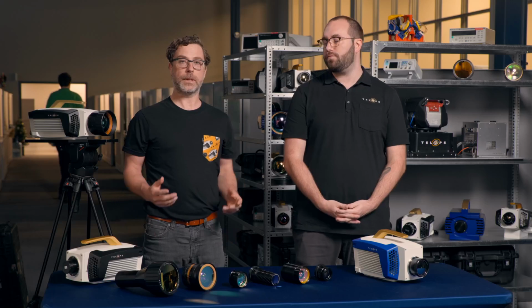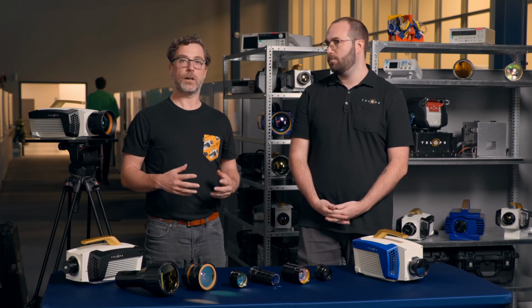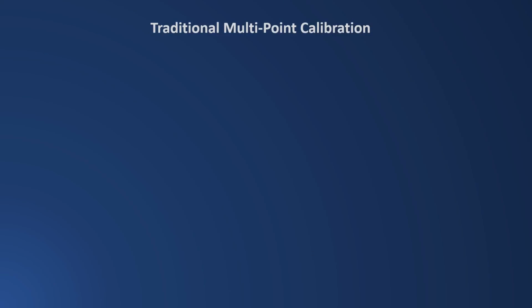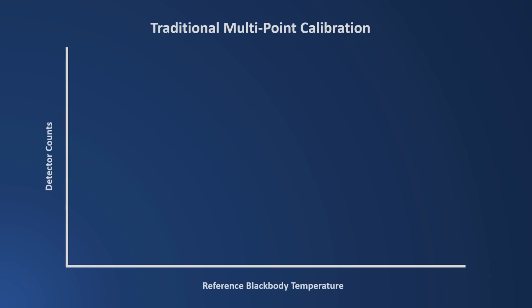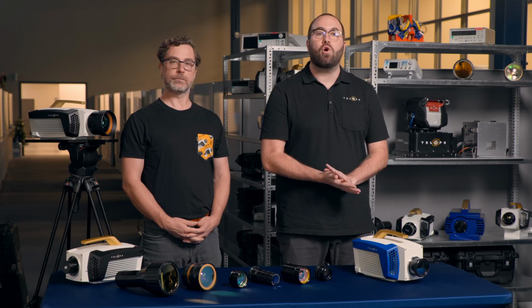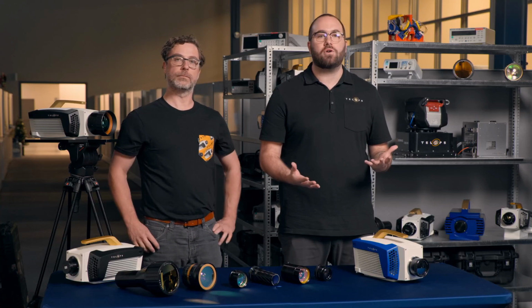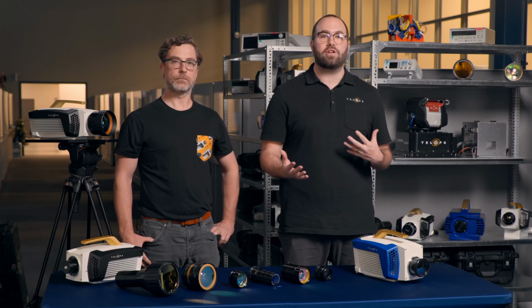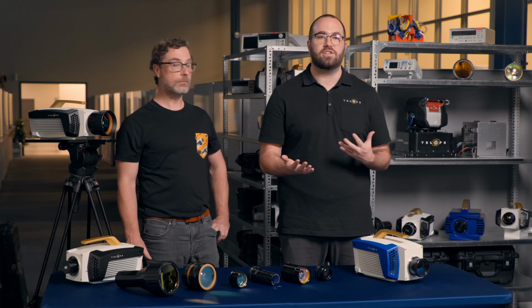the detector. The typical infrared calibration scheme is called a multi-point calibration and requires the user to analyze multiple blackbody reference sources. Multi-point methods are considered local calibration methods because they provide strong accuracy performance when the measurement conditions match the calibration conditions. Multi-point and other local calibration methods provide good results for a fixed instrument operating configuration, things like the window size and the exposure time.